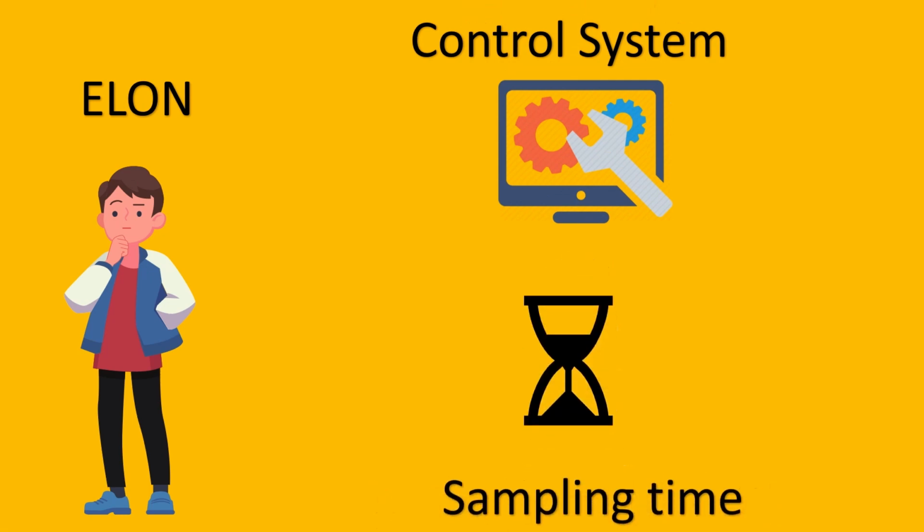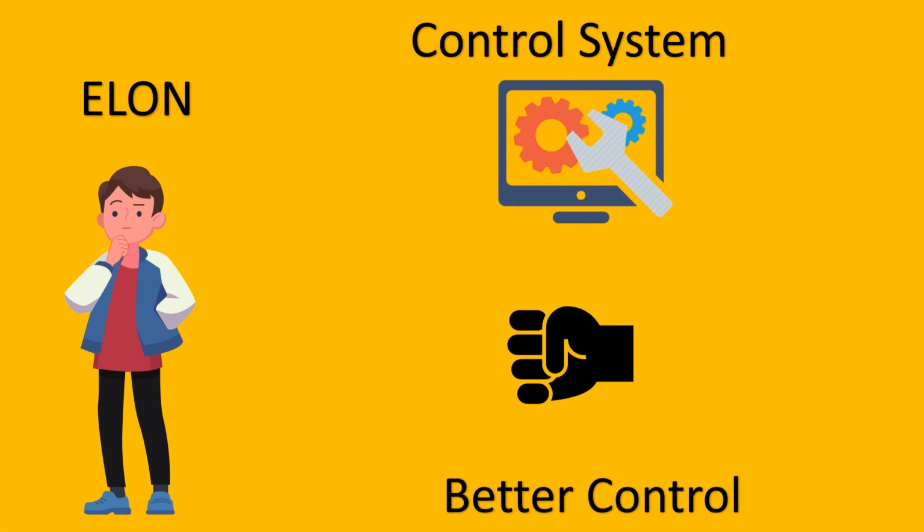However, there is one more thing to be known about the control system: there is a small issue with respect to sampling time, because the DP signal is first transferred to the control system and then the square root happens. However, this is very little, and usually orifice meters are not used for extremely high accuracies, so this has never been a point of concern usually.